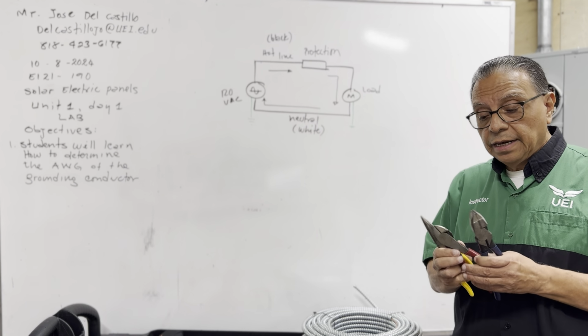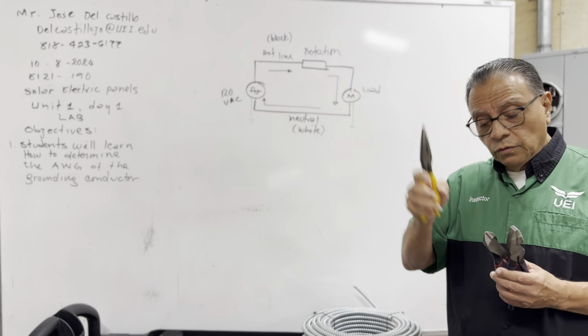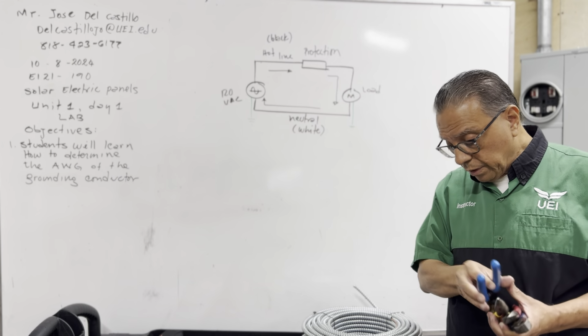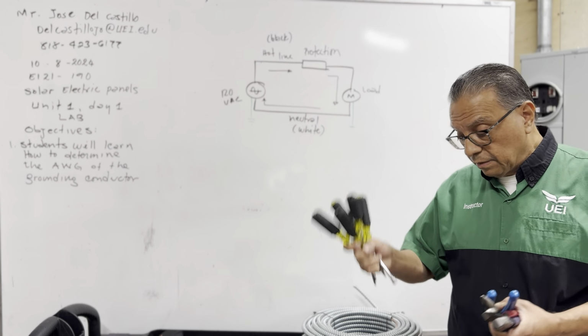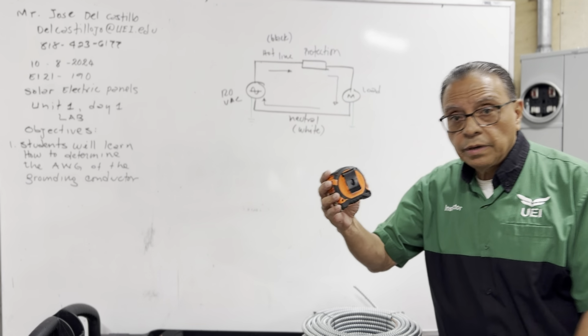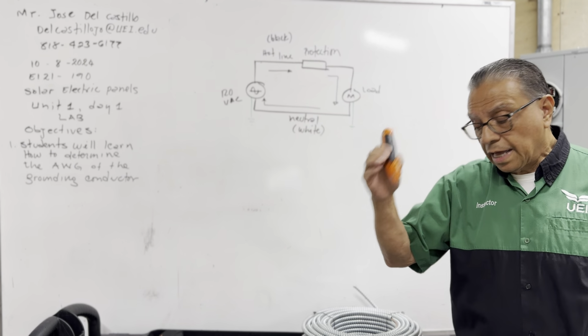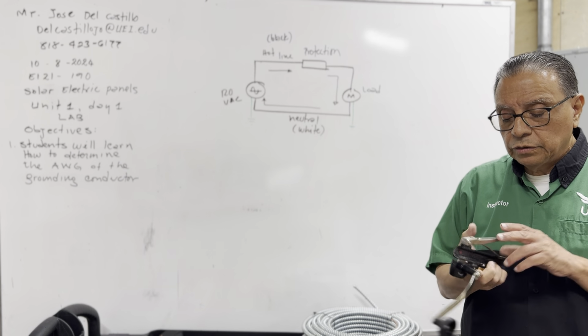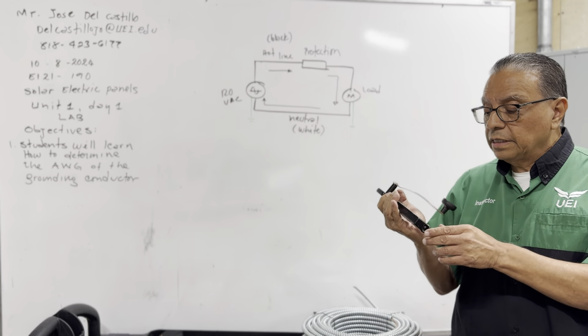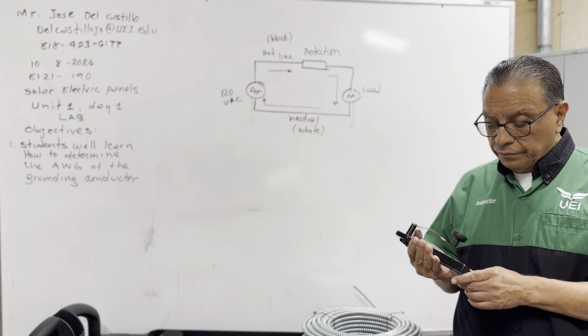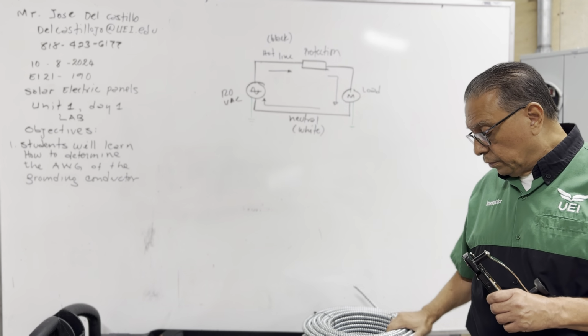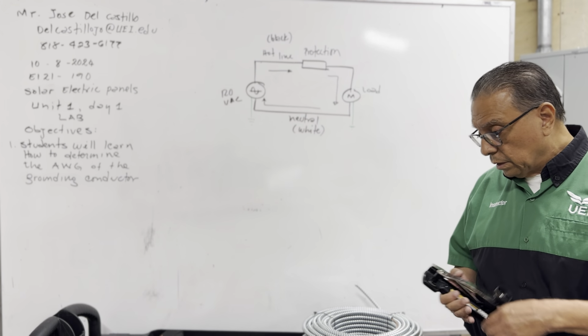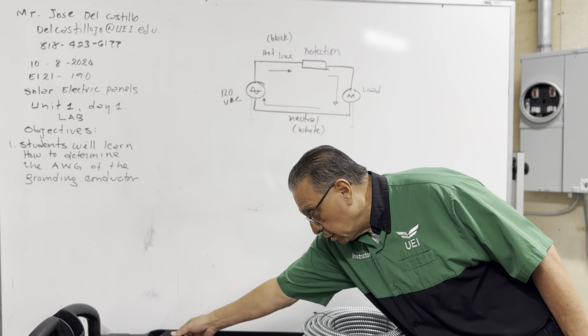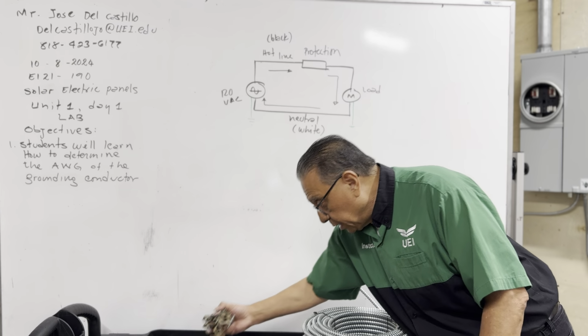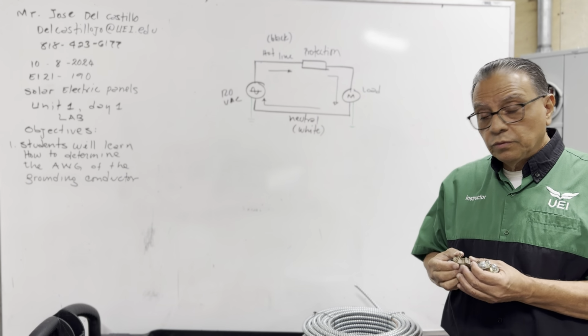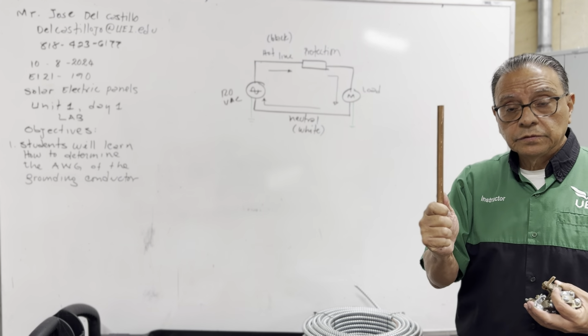Each tool kit has to have the lineman, the dies, the long nose, wire strippers, a set of screwdrivers, Phillips and flat, measurement tape, a knife, and also in this case we are going to need this tool, the BX tool. We need this tool to work on the grounding conductor, the armor grounding conductor. Part of the material, I need the grounding clamp, the grounding bushing, and the copper rod.